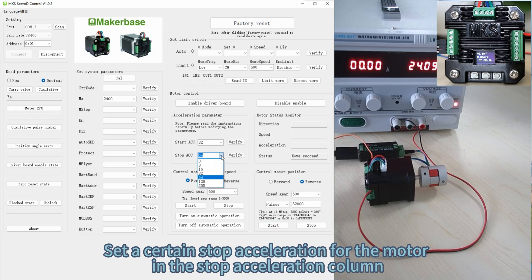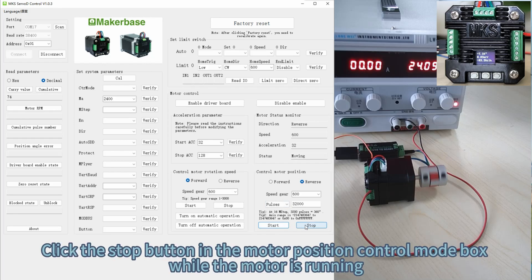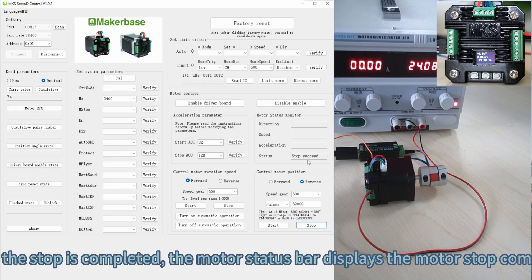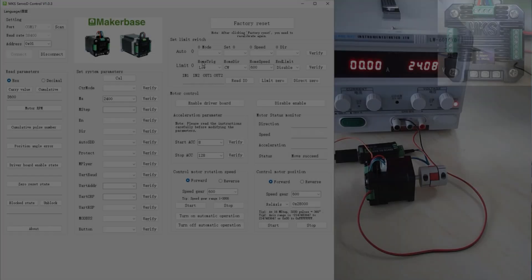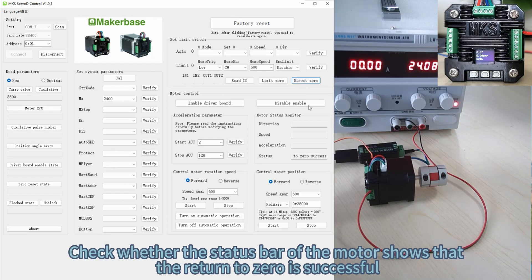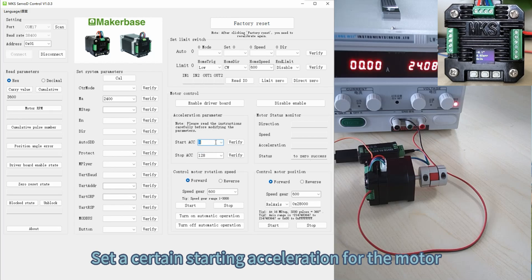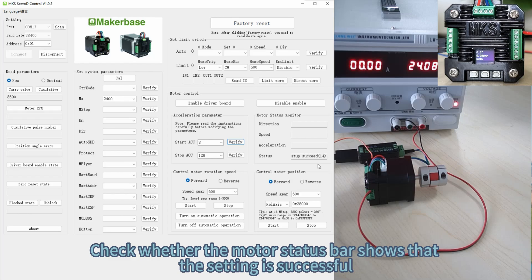Check the motor screen to see that the motor has run to the expected position. Set a certain stop acceleration for the motor in the stop acceleration column. Click the Stop button in the motor position control mode box while the motor is running. After the stop is completed, the motor status bar displays 'motor stop complete'. Click the Direct Zero button to set the current motor position to zero, and check whether the status bar shows that return to zero is successful.